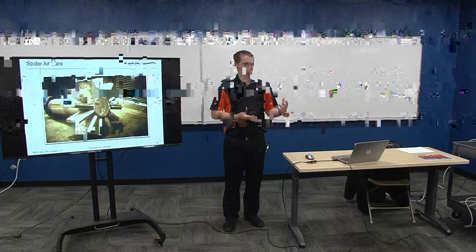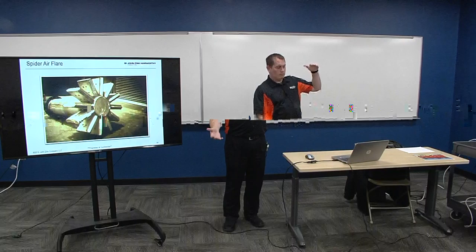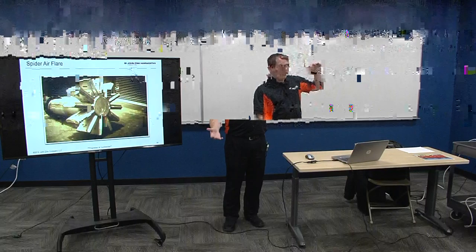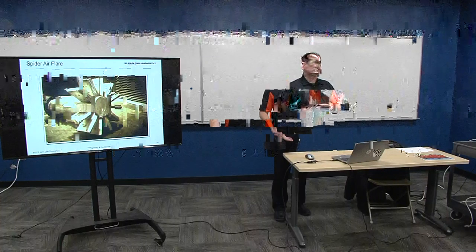To get the same amount of air as steam jets would in entraining air into the system, you would need some huge blowers, and that gets really expensive, right? So air flares are a good option, but they're not as efficient as steam flares. So that's a little history on why things aren't just using blowers. Blowers are a good use when you don't have steam, but they're not as efficient as steam because it requires a lot of horsepower to push that same amount of air.